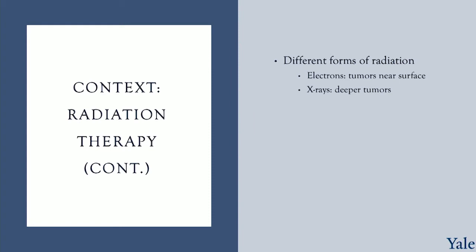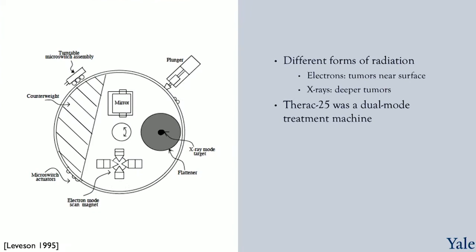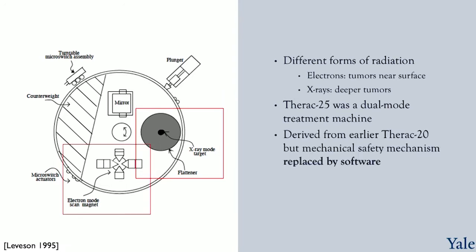Direct exposure to x-ray can cause serious harm to patients. Therac 25 was a dual-mode treatment machine, meaning it had both electron and x-ray treatment capabilities. You can see where there could be a potential problem here. The figure on the left shows the turntable setup, which has both the x-ray and the electron treatment regions. Notice the flattener that must be aligned with the x-ray source in order to prevent direct exposure, and the scan magnet that aligns with the electron source to direct its beams. A computer adjusts the turntable position. This machine derived from an earlier Therac 20 model. Therac 25 replaced mechanical safety mechanisms with software, which supposedly would check the turntable settings. Failures within the software caused several incidents of radiation poisoning when the electron magnets were wrongly aligned with the x-ray, leading to severe injuries and death.